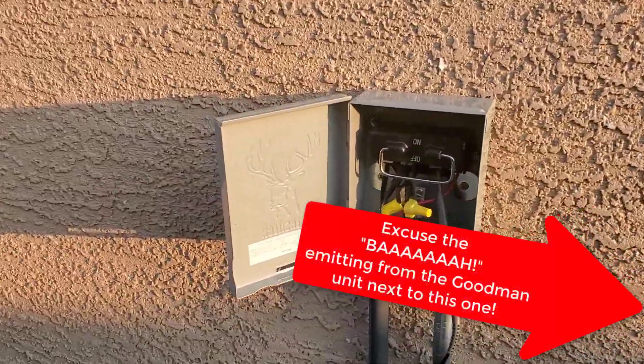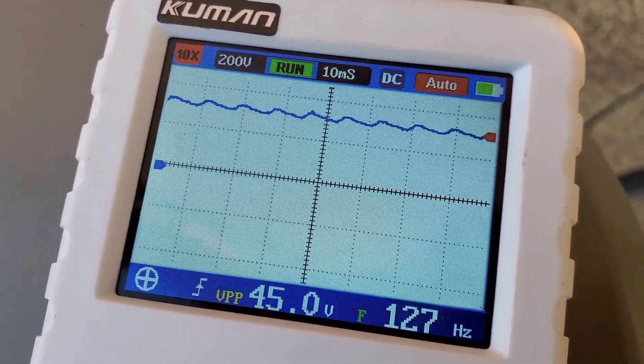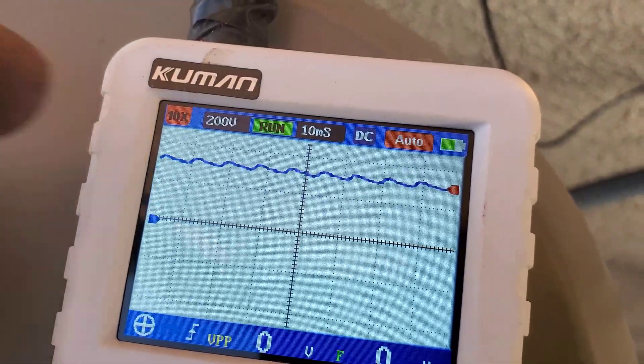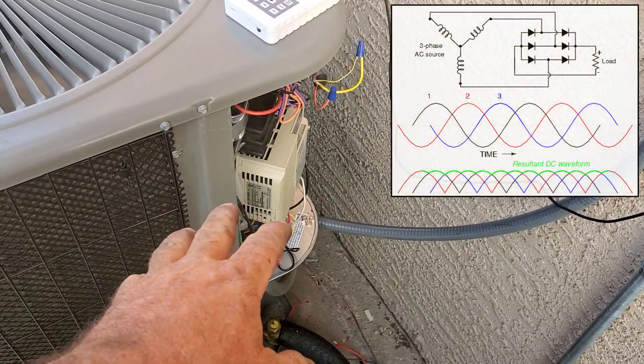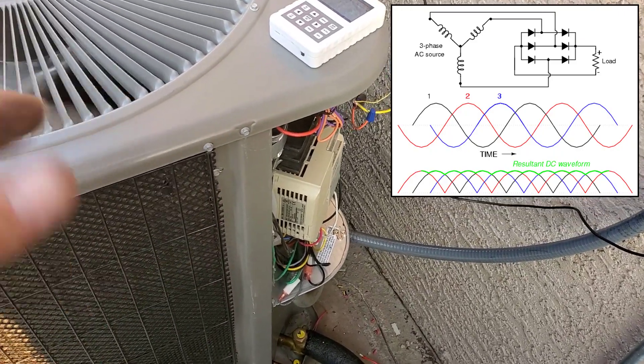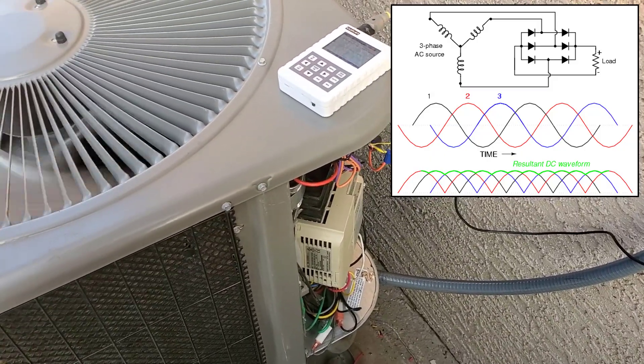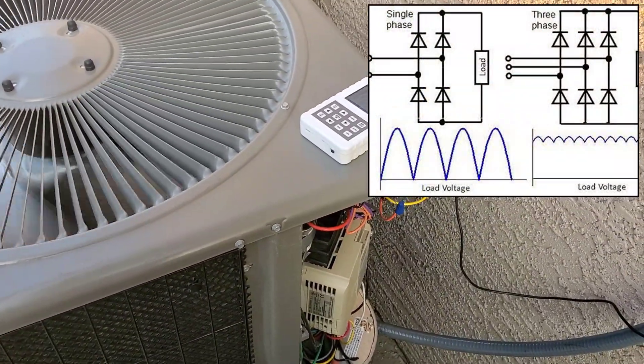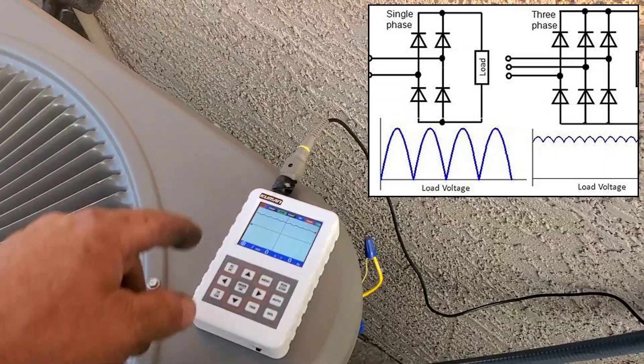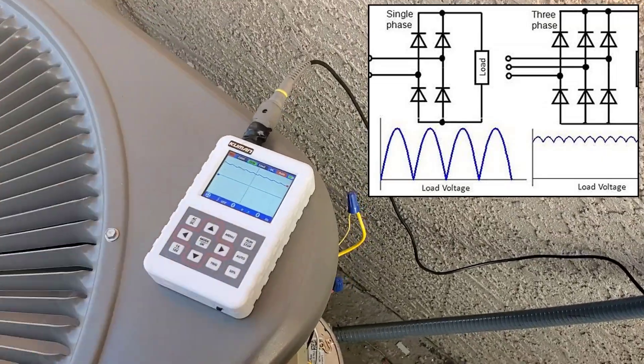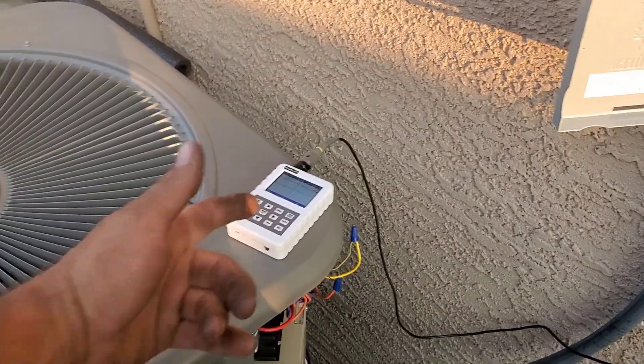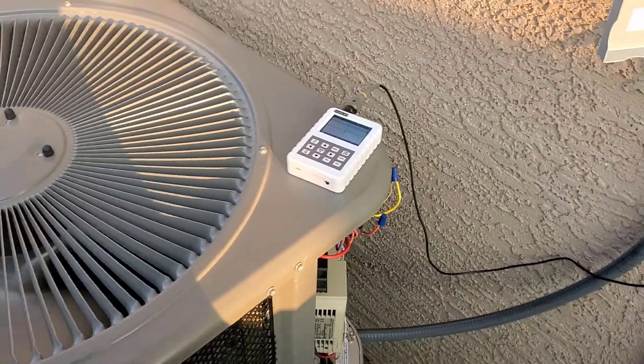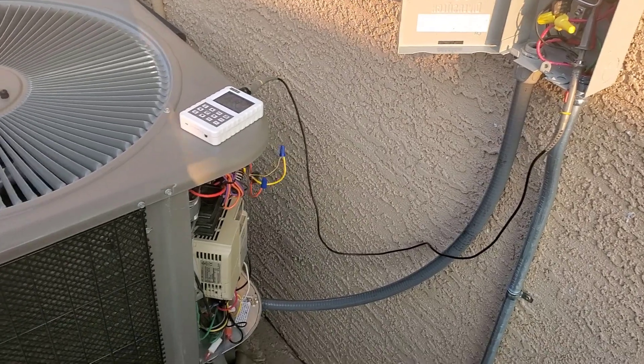Look at the DC bus now, see the ripple on it. Of course you know that has six diodes in there normally to charge the DC bus through three-phase power, through all the combinations through one time period. But I'm just doing single-phase input. I mean there's gonna be a longer gap in between each sine wave, just giving me one period still charging the DC bus, but you get the ripple and it's gonna have a lot of current. I'm still trying to get something hooked up to where I can actually see accurately the current spikes on an oscilloscope.